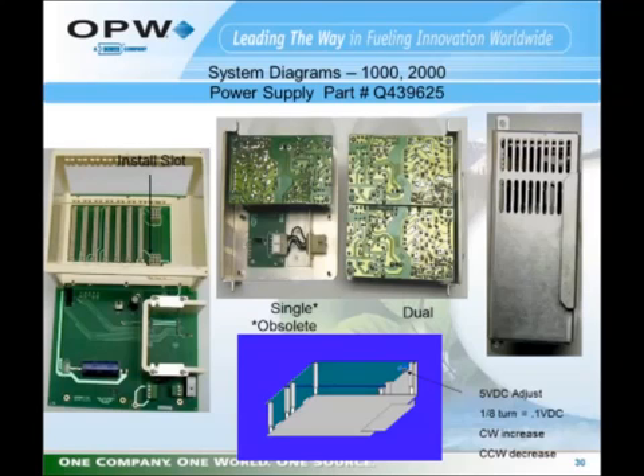In order to adjust the 5 volts on the power supply, what you'd have to do is remove power from the unit, remove the power supply, make the adjustment, reinstall the power supply, turn the power back on, and check your voltage. So it's kind of a trial and error method, but you can see that 1/8 of a turn is approximately 1/10 of a volt DC. That gives you a guideline when adjusting the power supply.